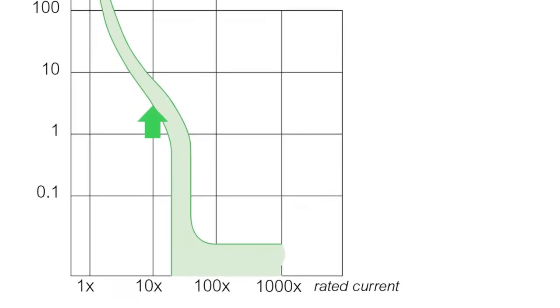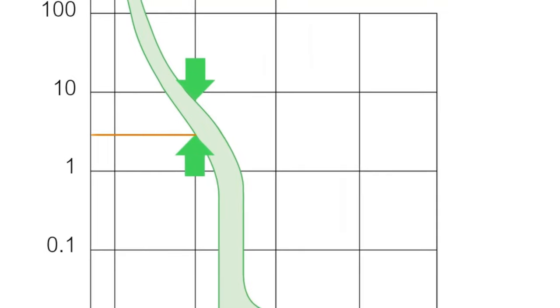For example, on this time-current curve, at an amperage 10 times the rating of the circuit breaker, using the logarithmic scale on time, we see a trip will happen sometime between 3 and 8 seconds.